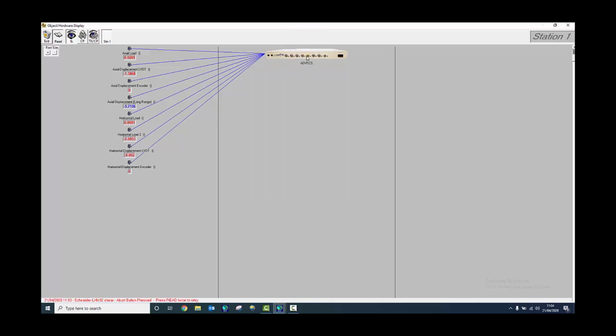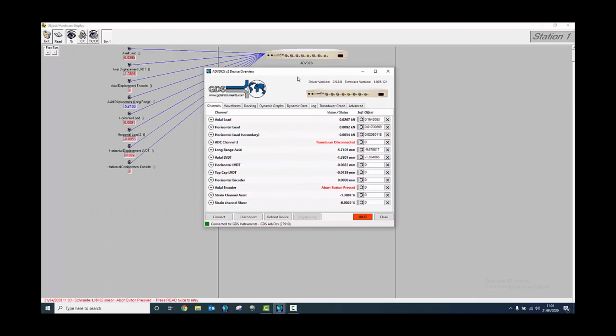If I left click on the icon of the box, that will pop up with the device overview window, in which you can see live readings from all of the transducers. And you can see there's a couple of errors about the abort button. The transducer on channel number 3, for example, is not connected. So now we can just do the sanity check on the transducers. We'll begin with the axial load. So you can watch the value on the screen and press on the load cell, on the axial load cell, making sure that the value goes up.